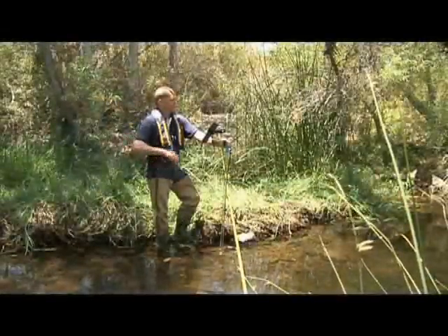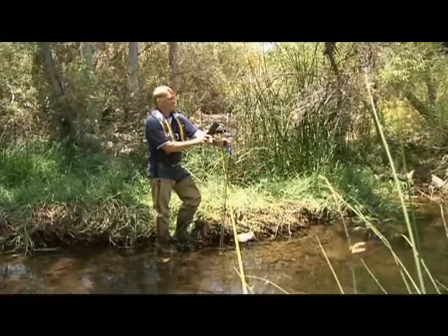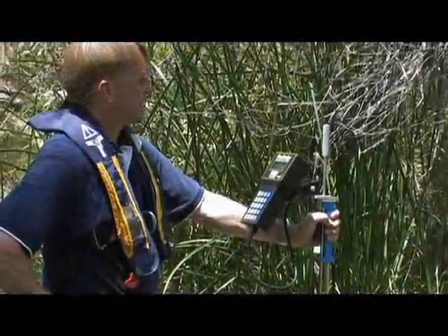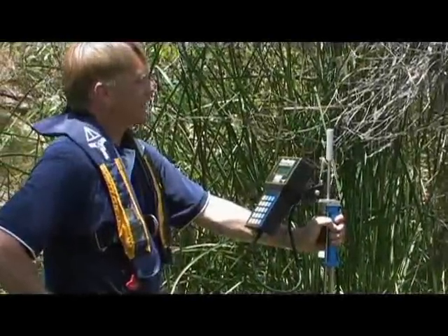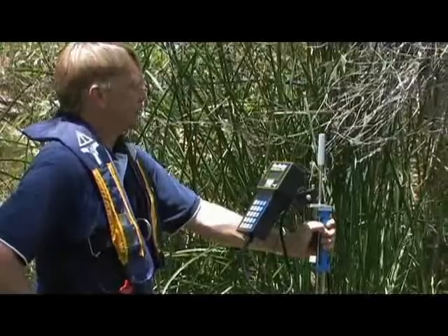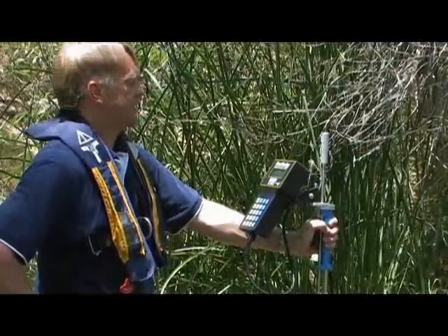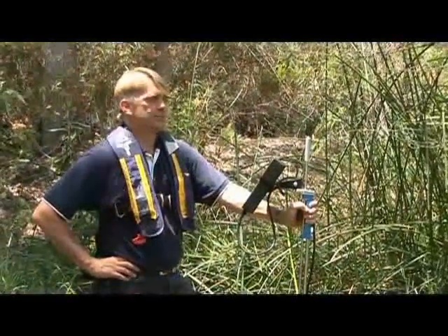I have to position myself so I won't obstruct the flow velocity, and I press measure to begin. Okay, now our measurement is complete, and it gives me a velocity reading of 0.032 meters per second. I have a velocity variation of 1,000th of a meter per second, an angle of 2 degrees, an SNR value of 18. The spikes were 0, and the boundary was best.